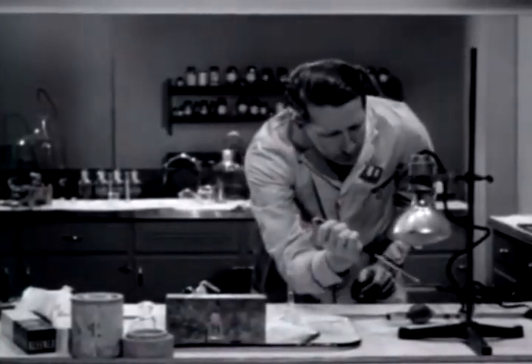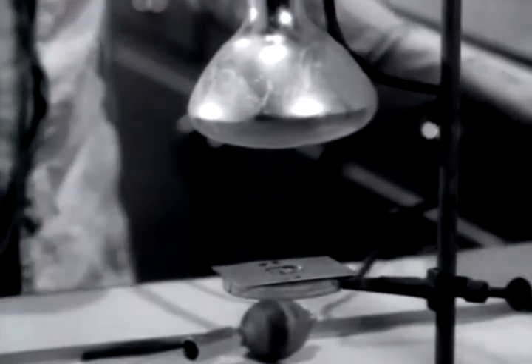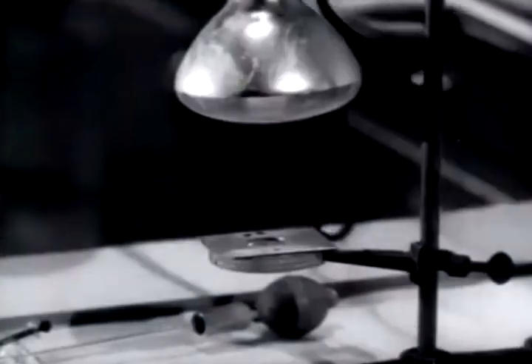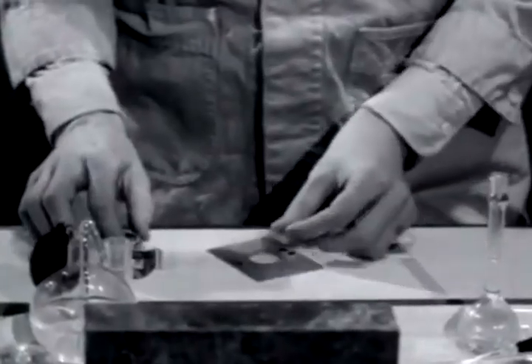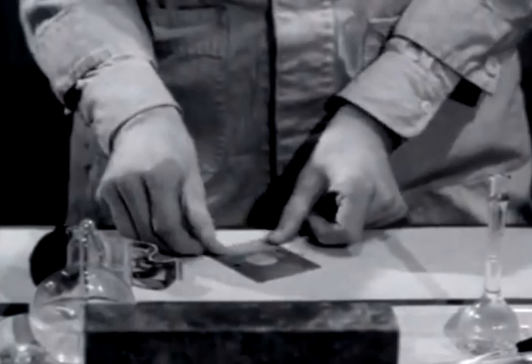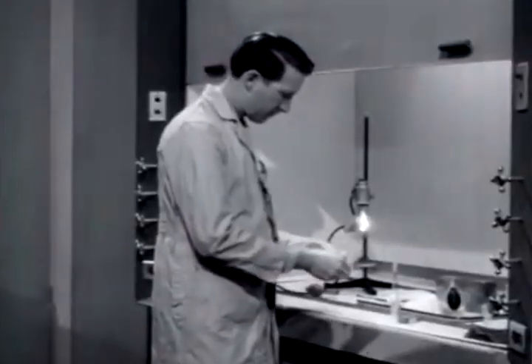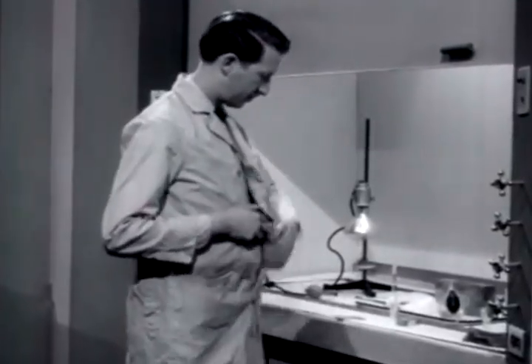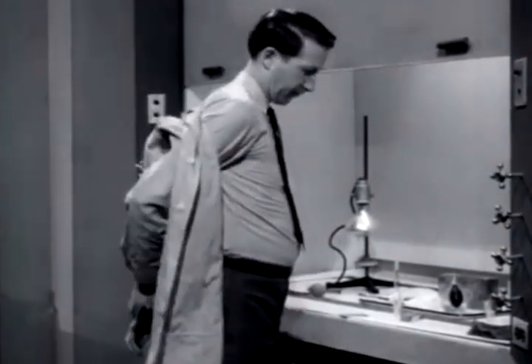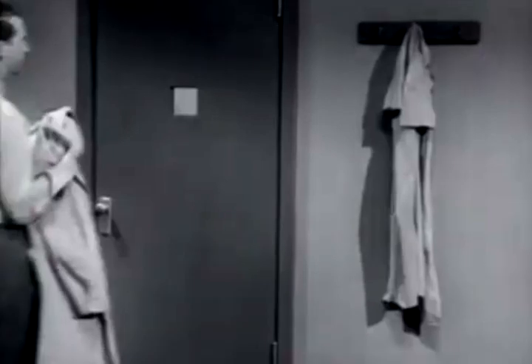The sample is pipetted onto the sample mount to produce the same thickness and area as with the standard. An infrared lamp is frequently used for drying samples. When the sample is completely dry, the investigator covers it with a thin sheet of cellophane held in position by cellophane tape to form a tight seal. This will avoid loss of the sample material, possible contamination of the laboratory, and inhalation or ingestion by laboratory personnel. To prevent contamination from being carried to the counting room, the investigator's smock should not be worn outside the chemical handling room.